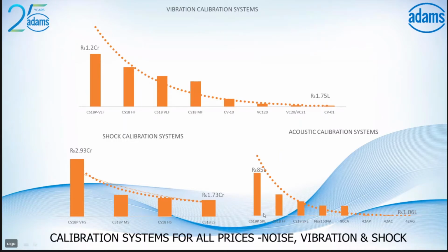We have a calibration laboratory in Chennai. So we have the acoustic vibration calibration system from Spectra. So this is the complete system. Here is the control unit and then the amplifier. At the end of calibration, the only effort that you have to make is to mount, then start by software. The calibration process will be completed and you will get a beautiful report like this. We also have the capability to calibrate a microphone. With the Spectra system, you can calibrate ICP and charge type, piezo, PR type, and DC MEMS type accelerometers.